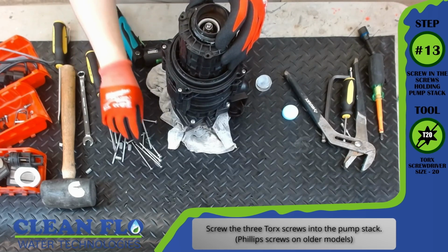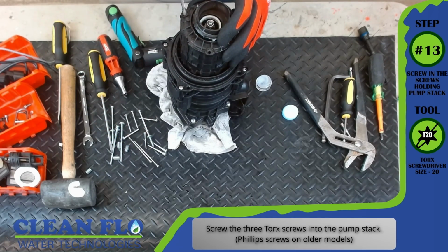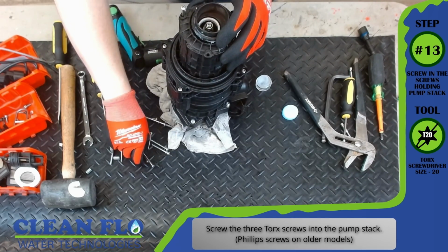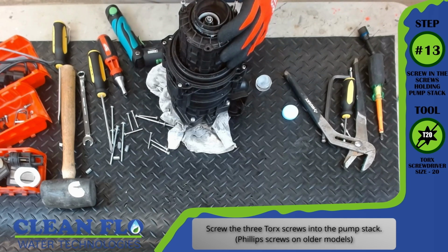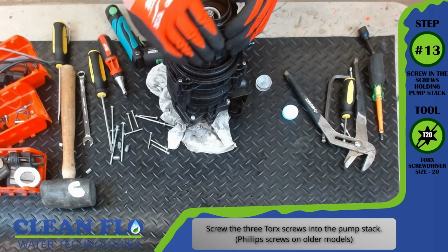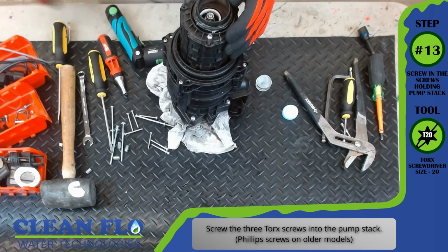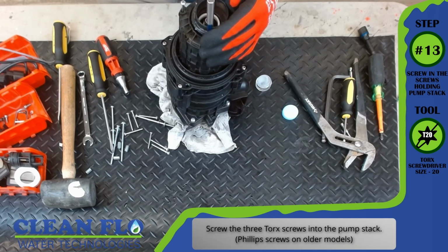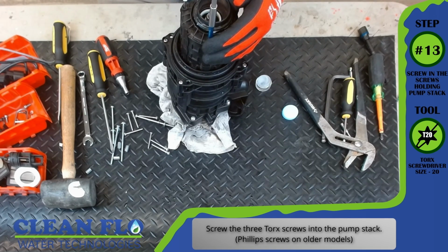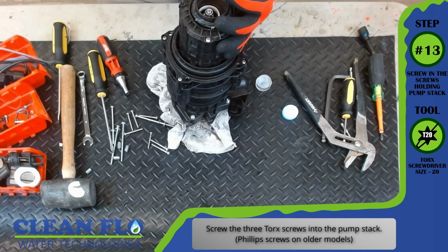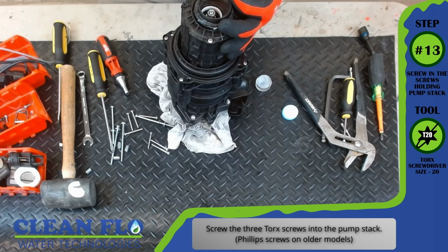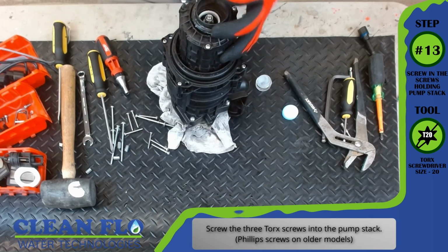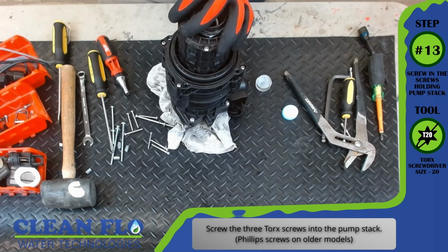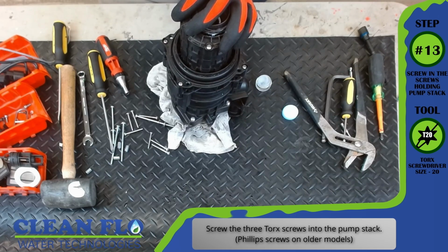Step number 13, screw in the screws holding the pump stack. Tool, T20 Torx screwdriver. Screw the three Torx screws into the pump stack. Phillips screws on older models. These 3 screws will hold the pump stack into place, but allow the impellers to freely spin inside the stack when the motor rotates.